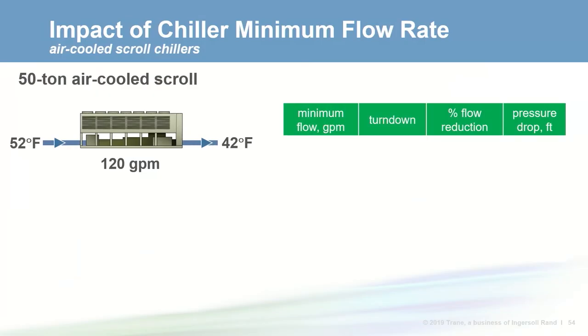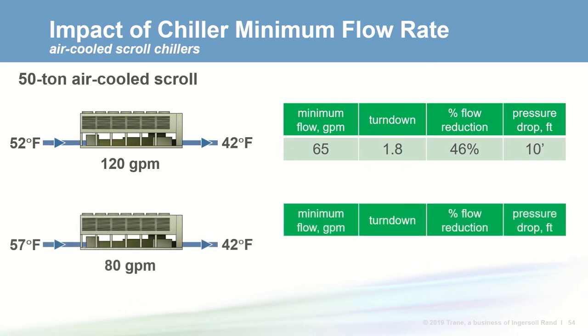The example here is a 50-ton air-cooled chiller with a brazed plate heat exchanger — probably the least configurable product in terms of evaporator selection. The original design has a design flow of 120 GPM. The minimum flow for this chiller is 65 GPM, giving a flow turndown of 1.8 to 1, or a 46 percent flow reduction. Using the exact same chiller but reducing flow to get a 15 degree delta T — 57 entering, 42 leaving — the design flow reduces but the minimum stays at 65 GPM, and the flow turndown drops to only 1.2 to 1, well below the recommended 2 to 1 for variable primary flow systems.